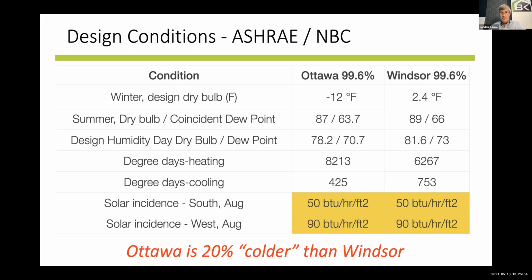The second number, of course, summer to dry bulb. This is, again, 87 degrees. The number beside it is the coincident dew point. You will know what dew point is. That's the point at which we'd see condensation. On a hot day in Ottawa, the dew point on the design day, the 99.6% design day, on the hottest day, the dew point outside is 63.7 or 64 degrees. Okay. Go down one number, one row.